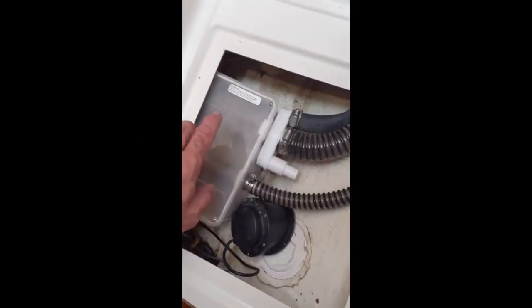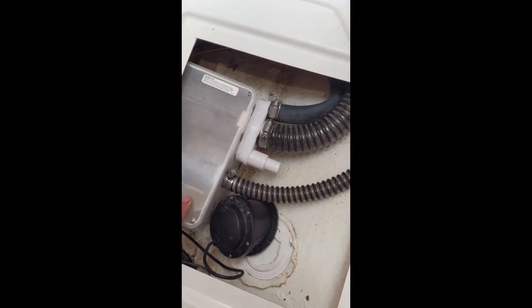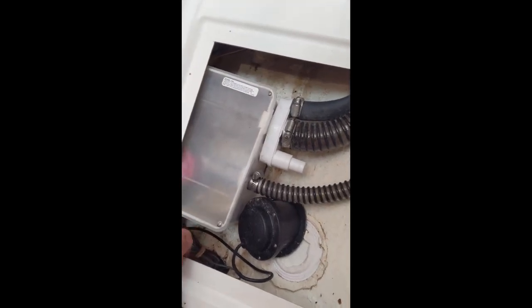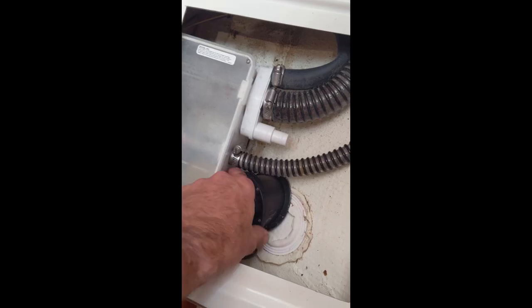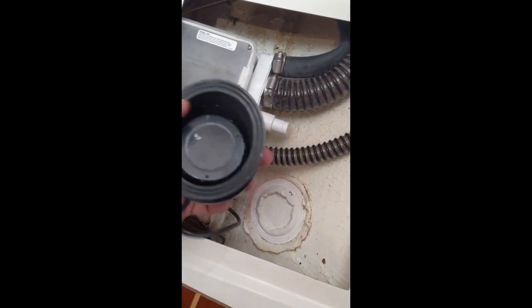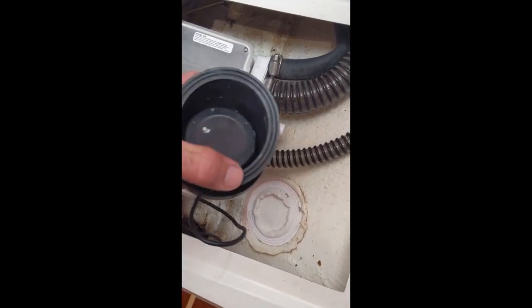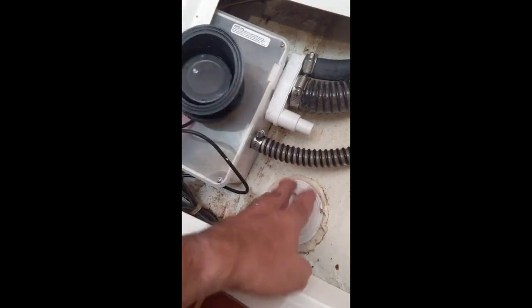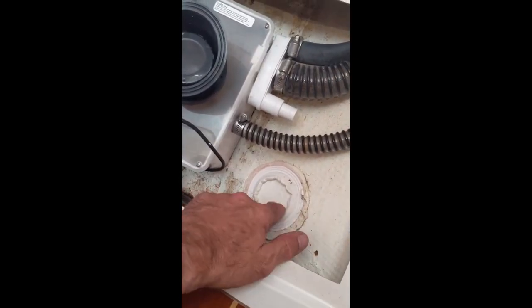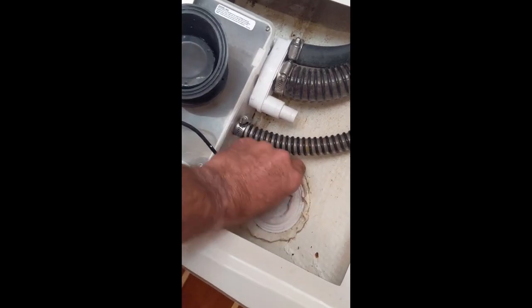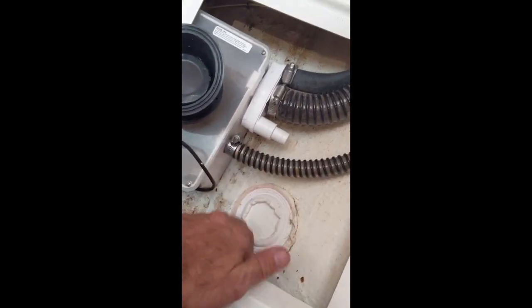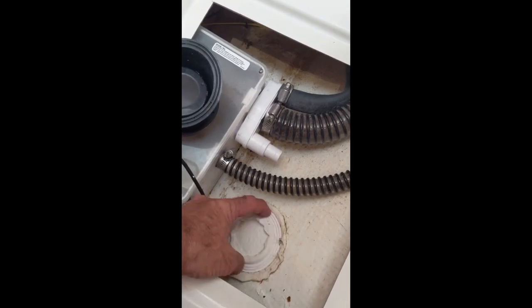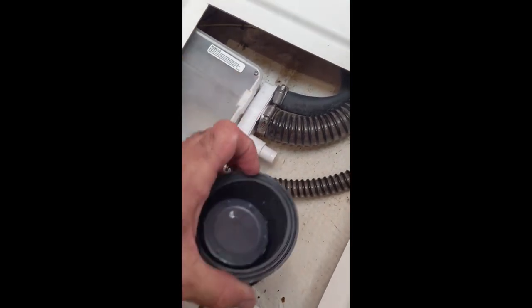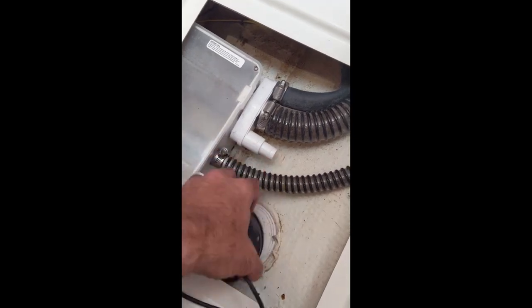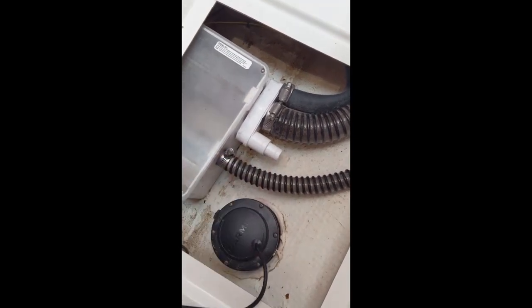Here I was checking the sump pump, making sure it's level and draining, which it looks like it is. But the transducer here has come off its seal, and this wasn't even sanded and sealed. So I'm going to have to strip this down, clean it up with some alcohol, sand it, get it roughed up, get some GE Silicone 1 instead of this garbage, lightly sand the base here, and re-secure this down. So anyway, another project.